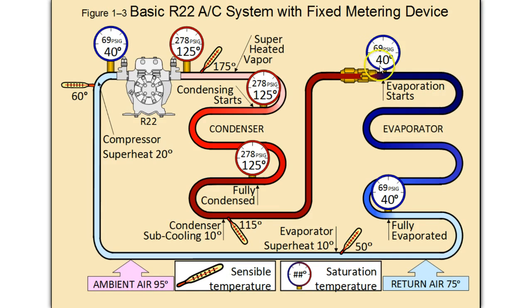Dropping the pressure automatically drops the temperature of the refrigerant, and it is at its saturation point immediately. So it is changing state immediately at the beginning of the evaporator coil, from liquid to vapor.